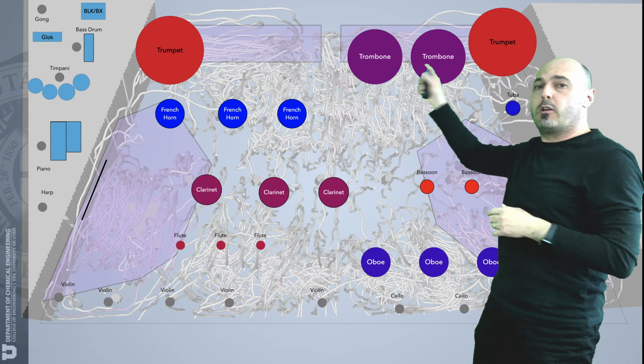And when we saw this, it was such a relieving thing to see that we could do this. All right, so next I'm going to show the breathing zone time and spatial average. This is the original arrangement, the simulation, and this is the open doors and the U-seating arrangement. If you do the calculation right, you can show that we reduced on average the accumulation of droplets by a factor of 100. And that was significant.